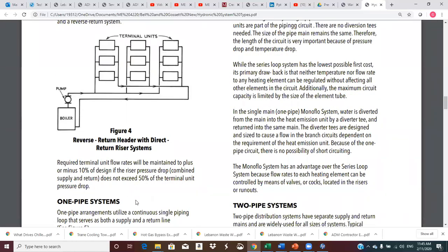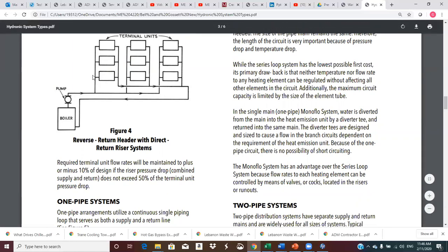It says required terminal unit flow rates will be maintained to plus or minus 10% of design if the riser pressure drop, combined supply and return, does not exceed 50% of the terminal unit pressure drop. So the riser pressure drop, supply and return, would be the pressure drop here to here on this pipe, and the pressure drop here to here, compared to the coil pressure drop.